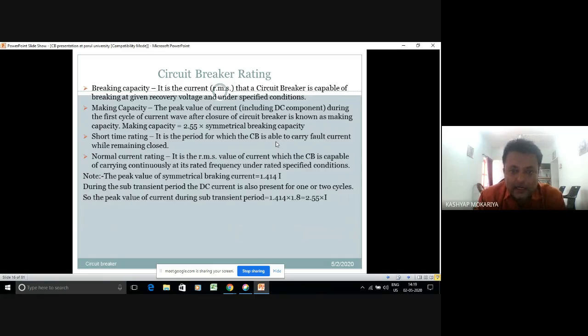The making capacity is the peak value of the current, including the DC component, during the first cycle of the current waveform after the closure of the circuit breaker. Making capacity is 2.55 times the symmetrical breaking capacity. I will share why this making capacity should be higher than the breaking capacity. The reason is that when you perform a recloser operation, or when you close your breaker on fault, you have to deal with that much higher current as compared to the breaking current. That's why the making capacity of a breaker is 2.55 times the symmetrical breaking capacity.